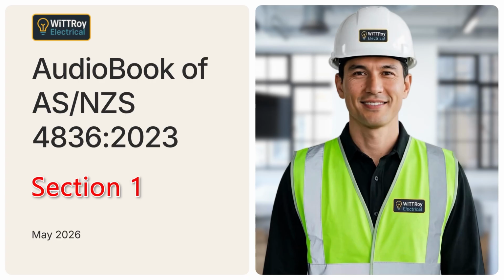Clause 1.4.29.1. Work near. Work near means doing a task within 3 meters of exposed, energized conductors or live conductive parts, or electrical equipment. This can include electrical work and also other work, such as cleaning, pest control, or similar tasks. The key idea is that even non-electrical work can become electrically risky when it is close to live parts. Clause 1.4.30.